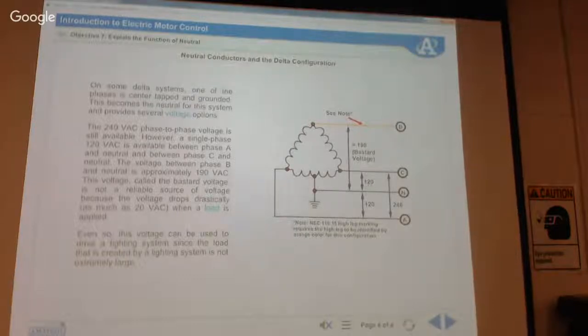Now, here, between this, and yes, that says the word bastard voltage. That is commonly what it is referred to and has been for a long time. I didn't make it up, it's right there. This voltage here on a transformer, they use that sometimes, and what they use it for is lighting. Typically you're not going to use a lot of it, but the ballast in your fluorescent lighting was able to handle that, and that's all they used it for. Certainly don't want to plug your computer into it.